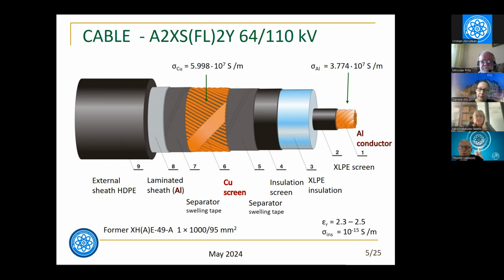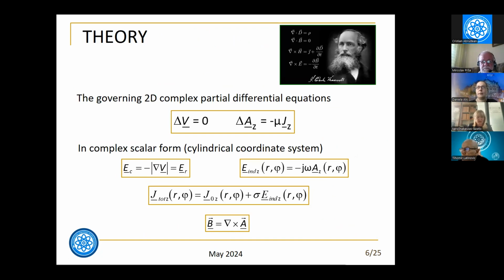As we can see, we have three metal layers in the construction of the applied cable. The permittivity of the insulation layers is between 2.3 and 2.5, and the conductivity of this layer is 10 to the minus 15 Siemens per meter.